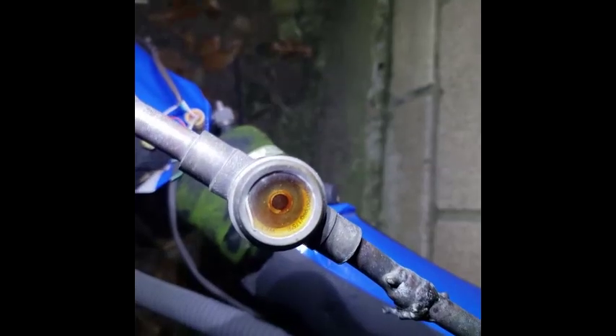So I think I had maybe about 3 pounds in this drum. That's it. All right, 75 over 193, I'm good with that. We started out at about, and I had put some in here too, and I was at 16 PSI on the suction. Sight glass not flashing, so I'll come by here tomorrow evening and look at the pressures and do a leak search. But until then, that's all.